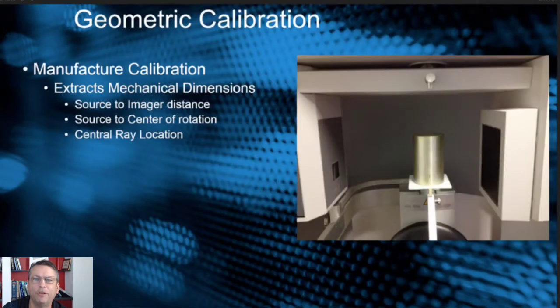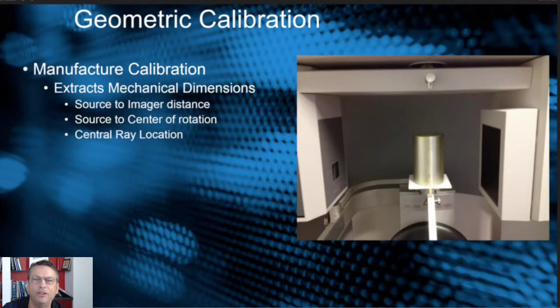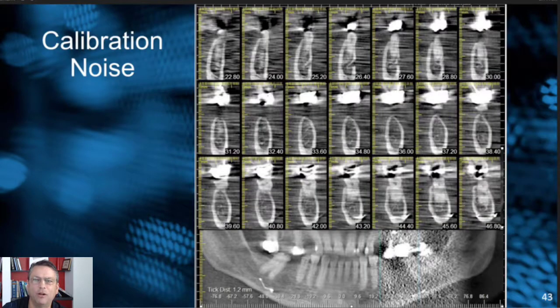A geometric calibration is something that the manufacturer can help you with. This is usually a cylinder that goes into your machine. Some manufacturers provide the cylinder for you, or they might have a tech come in and use the cylinder calibration. This particular calibration tool extracts mechanical dimensions of the machine, such as the source-to-image distance, the source-to-center-of-rotation, and the central ray location. These things help improve calibration accuracy.